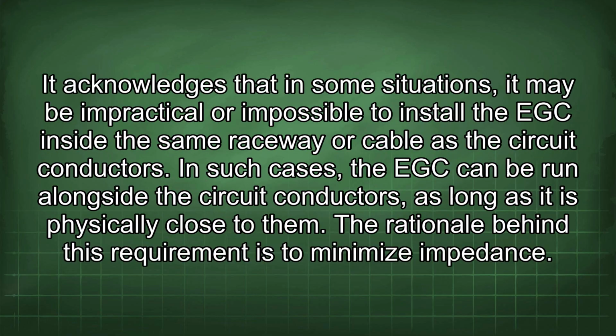It acknowledges that in some situations, it may be impractical or impossible to install the EGC inside the same raceway or cable as the circuit conductors. In such cases, the EGC can be run alongside the circuit conductors as long as it is physically close to them. The rationale behind this requirement is to minimize impedance.